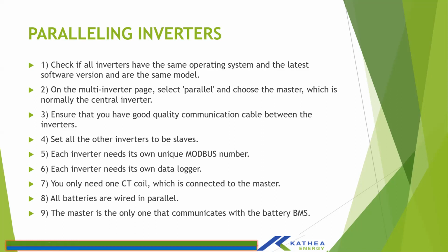And then obviously you need to set the inverter, whether it's a master or slave, and then the IDs. Preferably the master inverter should be installed in the middle. If you have two, there is no middle between the two, so it will be side by side. But if you have 3 inverters in parallel, then make sure your master is the middle inverter, such that the communication to the slaves will be quite fast. And make sure that you have got a quality communication cable between the inverters.